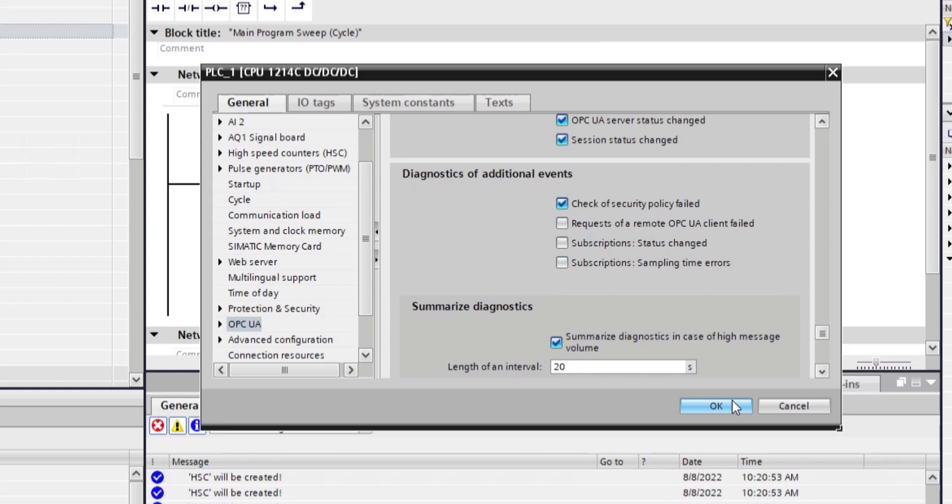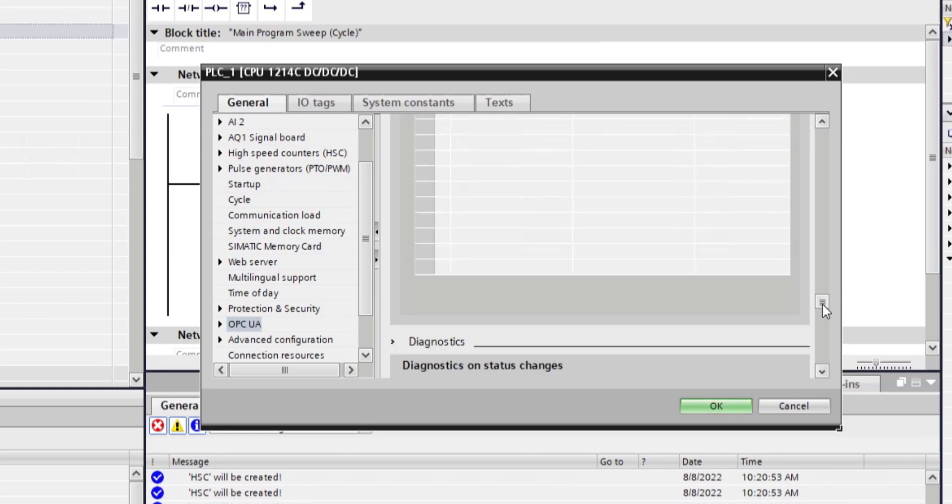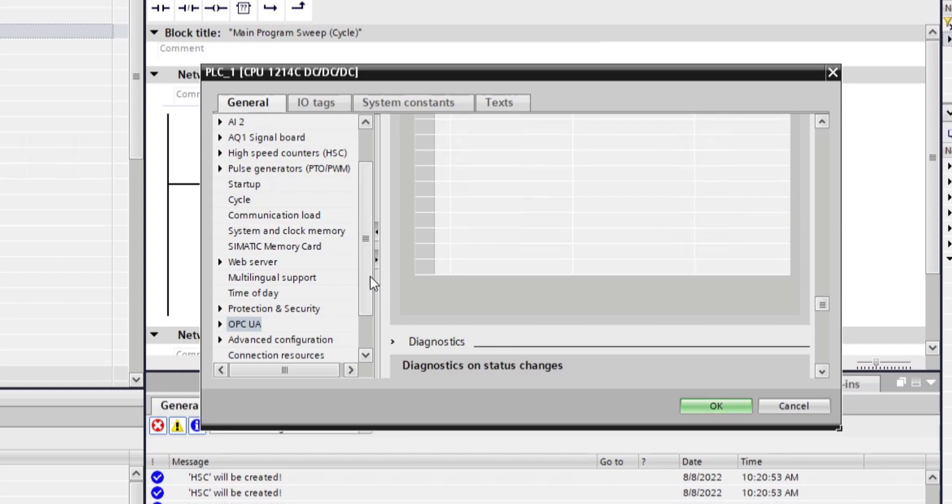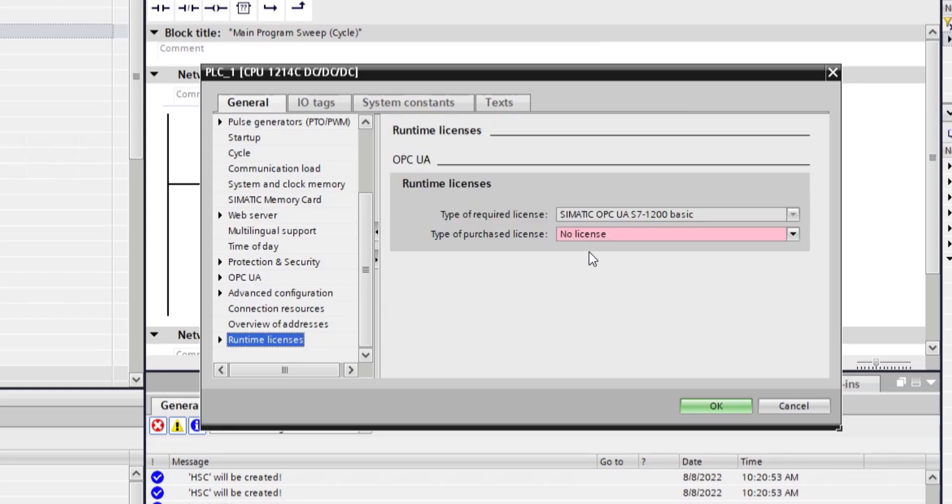Now I said the 1200 is slightly different to a 1500 and there isn't the standard Simatic interface. So normally on the 1500 there will be another tick box here saying enable standard Simatic server interface and then it exposes everything that's on your PLC onto one namespace. Again, it's not something I would recommend. Actually this way is much much better. But let's see what happens if we don't actually create a server interface. What will we get? One more thing we need to do.